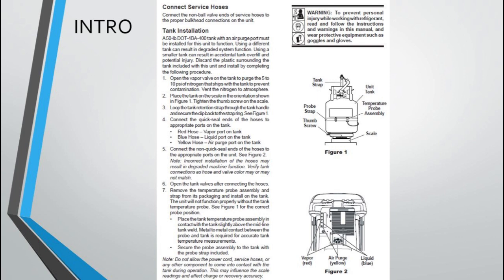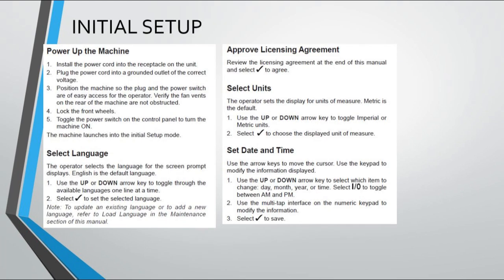Note: do not allow the power cord, service hoses, or any other component to come into contact with the tank during operation. Power up the machine. 1. Install the power cord into the receptacle on the unit. 2. Plug the power cord into a grounded outlet of the correct voltage. 3. Position the machine so the plug and the power switch are of easy access for the operator. Verify the fan vents on the rear of the machine are not obstructed. 4. Lock the front wheels. 5. Toggle the power switch on the control panel to turn the machine on.